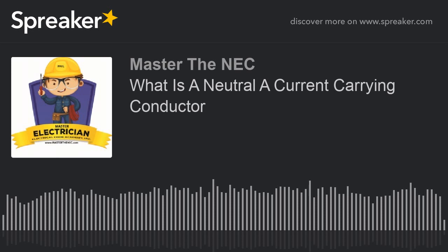But again, I showed you how that works, and I gave you some of the other aspects of what gets considered a neutral or not, or what gets considered a current carrying conductor. Obviously, that's a big topic. I could go into another podcast with those other things like groupings. But I wanted to touch on the concept and how you apply Note 1 to the table in 310.15(B)(3)(a), which tells you that those spares are counted, not just for raceway fill, but also when it comes to the number of conductors to apply this adjustment factor. It states it right there in the note.